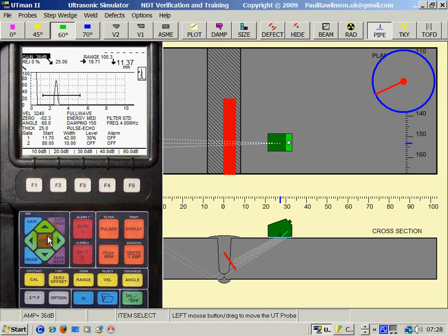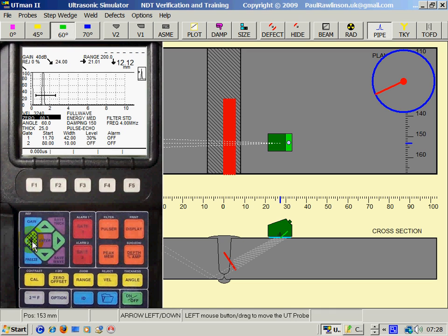For range, before we move off range, on the gain, it gives you quick F1 to F5 keys, 60 dB, 10 dB, 30 dB, 40 dB. On the range, we can then click left or right to change the range, or click on the quick keys button, for example F4 for 100, F5 for 200. Zero offset set, cursor keys to move left or right. Click on range again, I'll make the range 100.